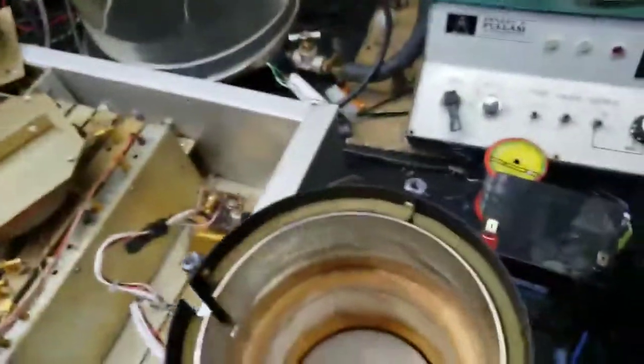I saw the burnt cavity in which the lamp was sitting — you can see how burnt that was. I think the dielectric failed on that wire, caused it to overcurrent, and it started melting. Down at the bottom there is a metal shield, and everything has to be magnetically shielded.